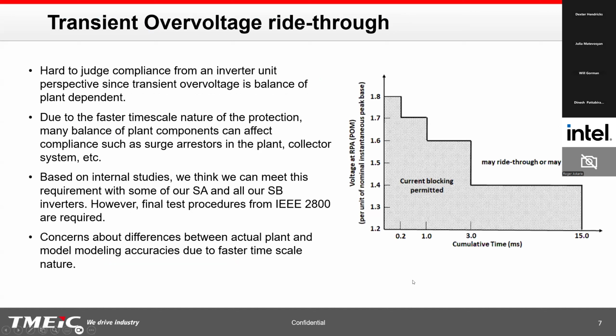Transient overvoltage ride-through is again something that is very hard to judge from an inverter unit perspective. It is not really covered by a standard in terms of inverter-level requirements. It depends very significantly on the plant itself, because plant construction can include components like surge arresters or even collector system equivalents that can affect transient overvoltage ride-through capabilities. So it depends on the design of the plant as well. At an inverter level, we don't have any tests available right now to study and meet this part of the standard.